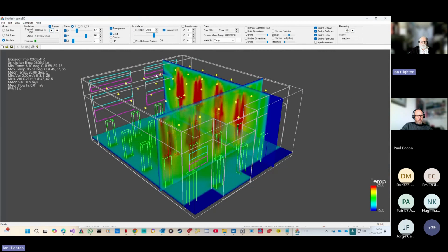So once the CO2 levels get going, then you'll find these windows will open up. You're seeing a bit of a cold plume coming off here, and that's only because the windows are cold comparatively. So I think it's 15 degrees outside, and as I say, it's the CO2 that they're being controlled on.